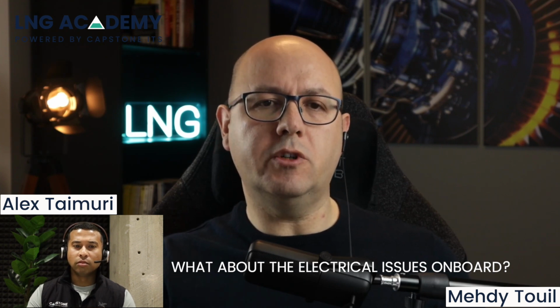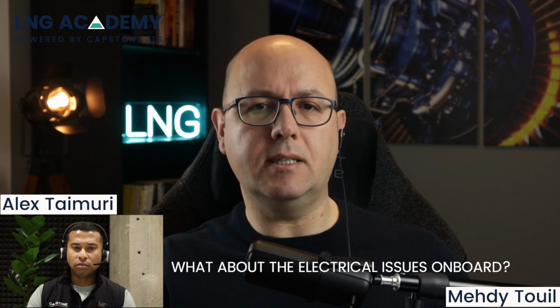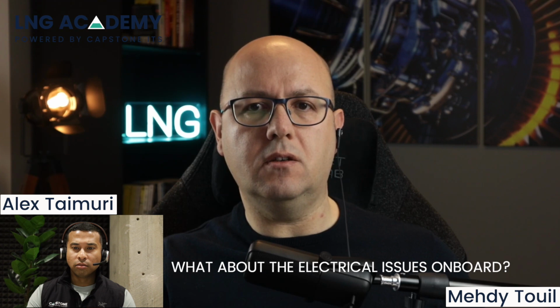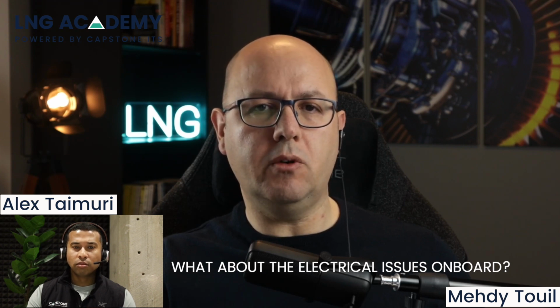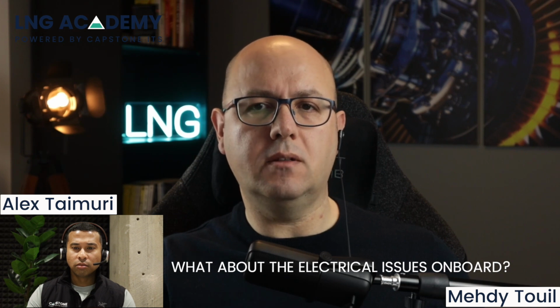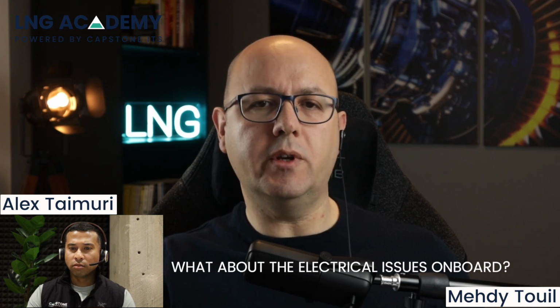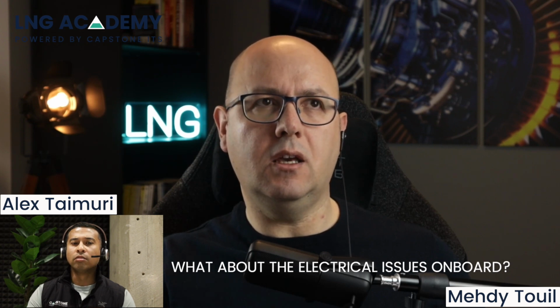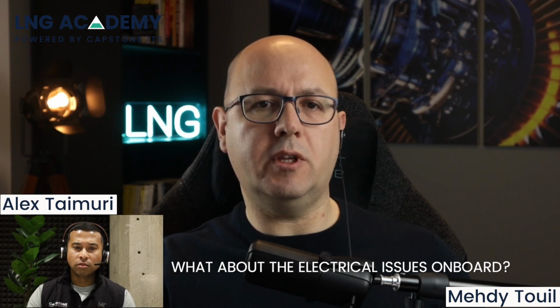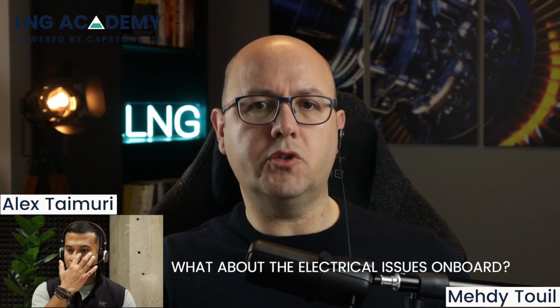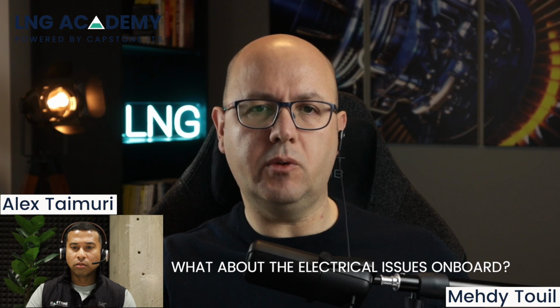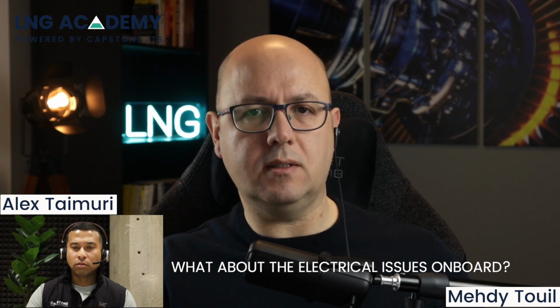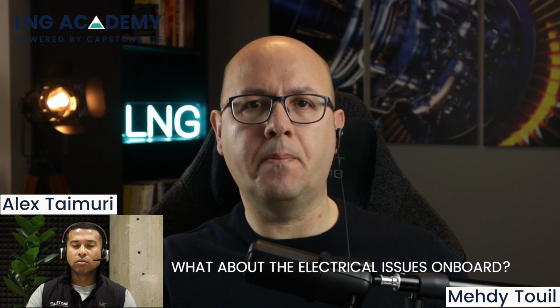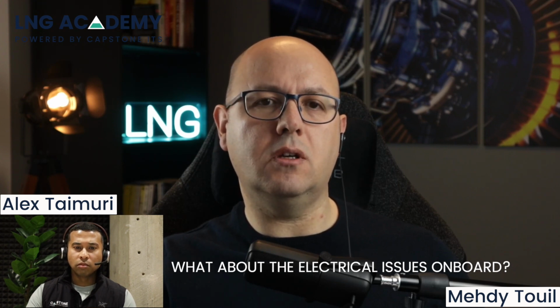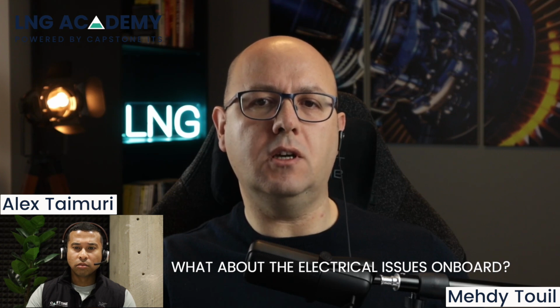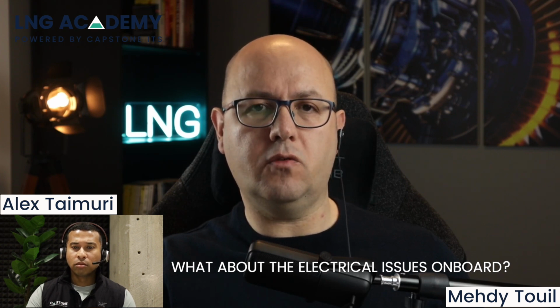You also don't want your emergency shutdown or depressurization systems running on batteries that will last for a few hours only. The offshore regulator concluded at that time that the operator, Shell, did not have a sufficient understanding of the risks of the power system on the facility, including failure mechanisms, interdependencies, and recovery. Shell was also asked to demonstrate that the facility can safely recover essential power and associated essential services following a loss of power, and that the safety systems and essential support system operate to maintain the safety of the personnel on board. That shutdown lasted for 4 months.